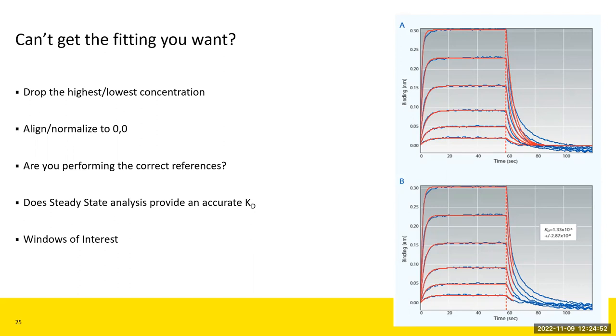Looking at the steady state or equilibrium, you can calculate a KD from just that portion of the curve. For windows of interest with very fast kinetics, it can be tricky to get a good off-rate - you can see the residuals are very large. If you shorten the calculation window to the first 5 or 10 seconds of dissociation, that's probably the most accurate, because as soon as the sensor hits the buffer the analyte dissociates - but it's still in the well, so if enough dissociates, some can rebind. So just look at the first couple of seconds.